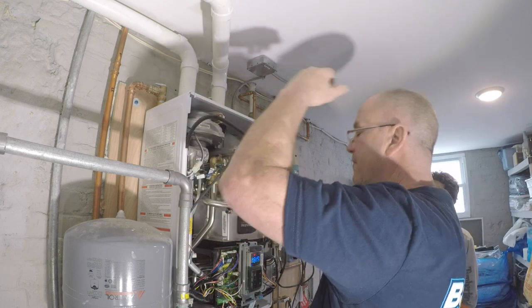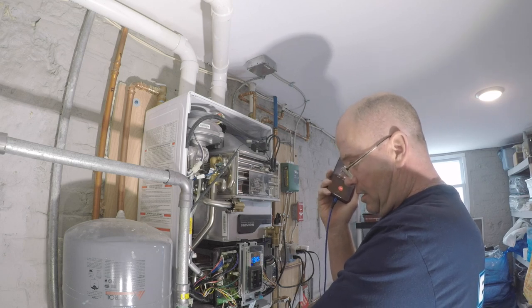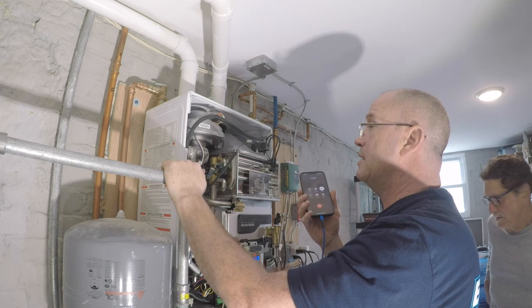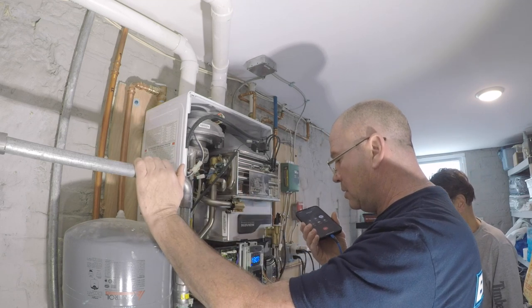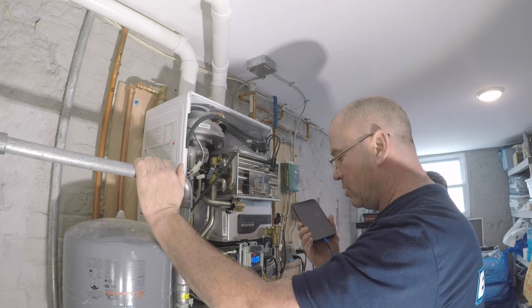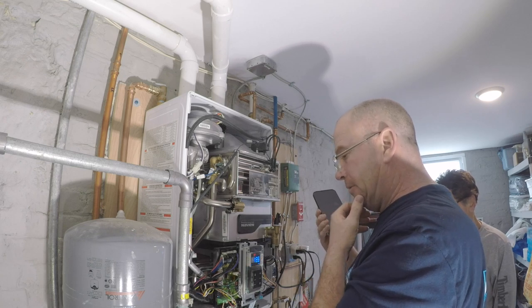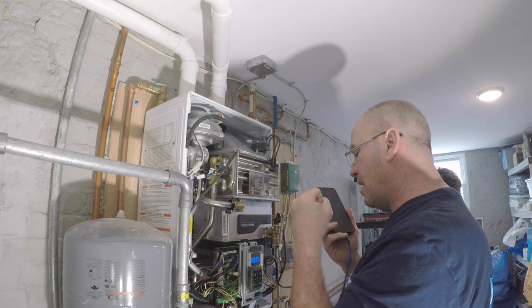We have a problem going on here — I believe it's the fan motor. I had called a couple months ago about a fan making noise and they ran me some prompts. It's acting up again today, and the fan definitely makes a noise when it comes on, almost like a Jake brake on a tractor trailer, and then stops. We have the heat off right now, nobody's calling for water, and the fan's still running, which I find very odd. The thermostat's turned all the way down. The main reason for my call was the fan making a vibration sound on startup of heat.